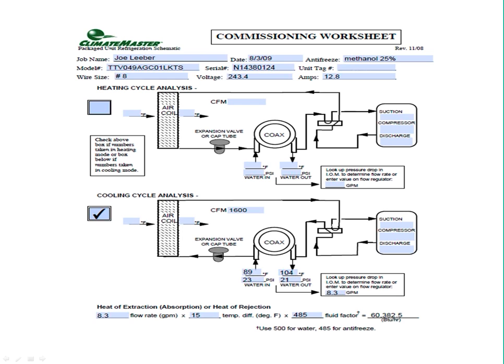Well, if you convert that pressure difference, again on the tables in your IOM, you're going to find that the flow rate's just about 8 gallons per minute. On a closed loop system, because this has methanol in it, you want about 3 GPM per ton. So this one's a bit on the low side, which would explain the 15-degree temperature difference going through that coax. You have typical flow rate of 3 GPM per ton. You have your typical 400 CFM per ton for the airflow. You should see on average, it's pretty common to see around a 10-degree difference on cooling. So when you see the 15-degree rise, that typically means you have too low loop flow.